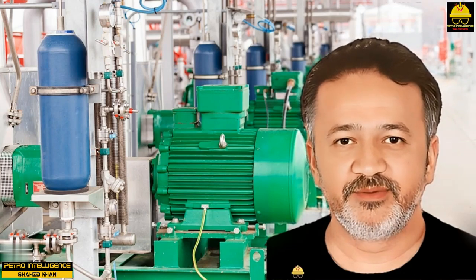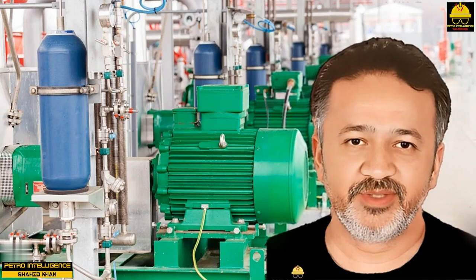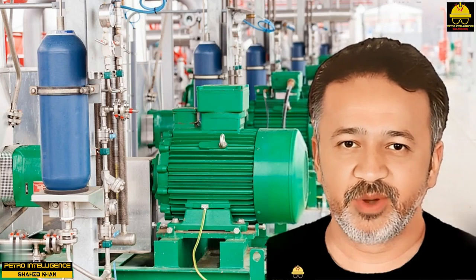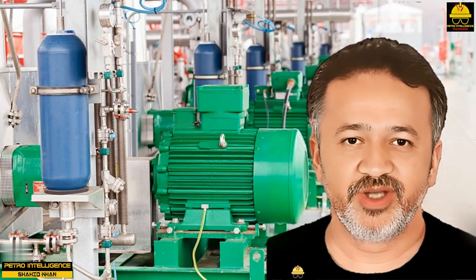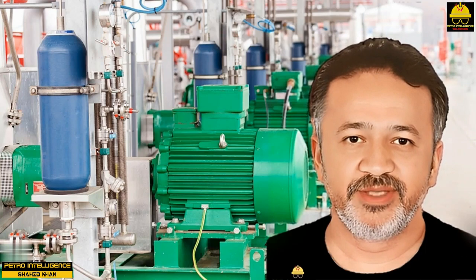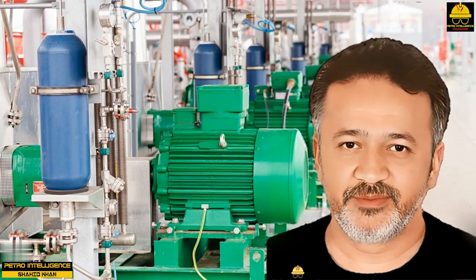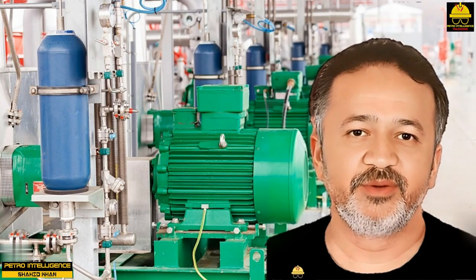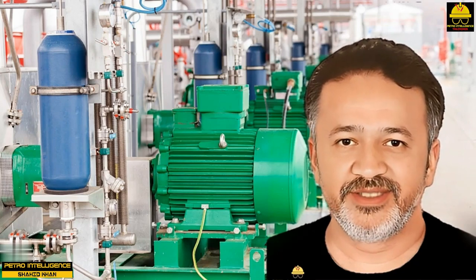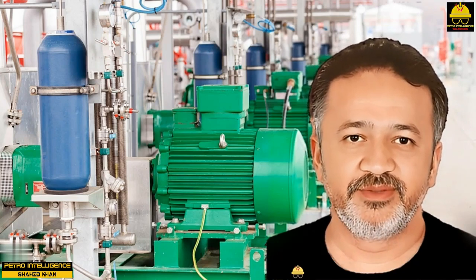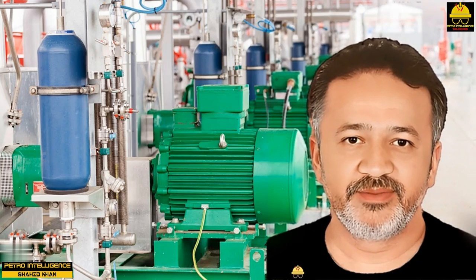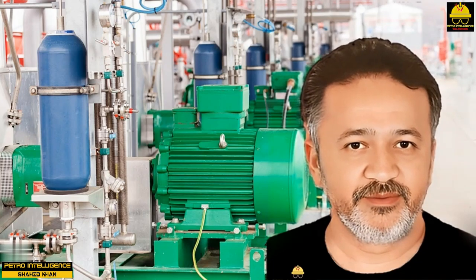Cavitation is defined as the formation and collapse of gas pockets around the impeller of a centrifugal pump. Cavitation occurs when suction pressure drops below required NPSH. At this point, the liquid vaporizes and forms gas pockets inside the pump casing. As these pockets form and collapse, the pump can be severely damaged.